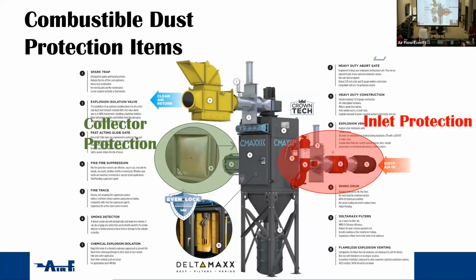You have the collector itself. In the event that an explosion occurs in the collector, you want to control where that explosion goes. If you don't have a sacrificial piece of metal or an explosion panel that will break away and direct where that goes, this whole collector could break up into a bunch of small pieces and actually become shrapnel and go all over. You have no control over it. So locating where this goes, the direction this faces in relationship to buildings, walkways, or other objects, trees, makes a big difference when you go through your design.